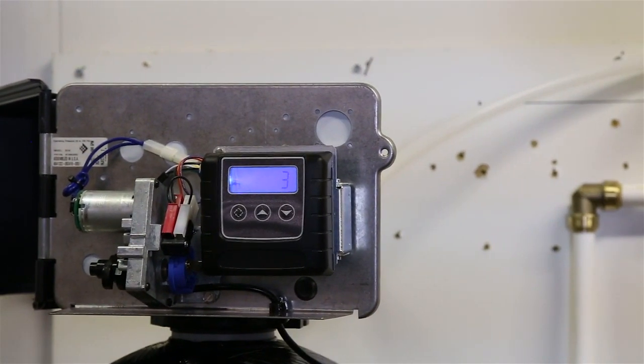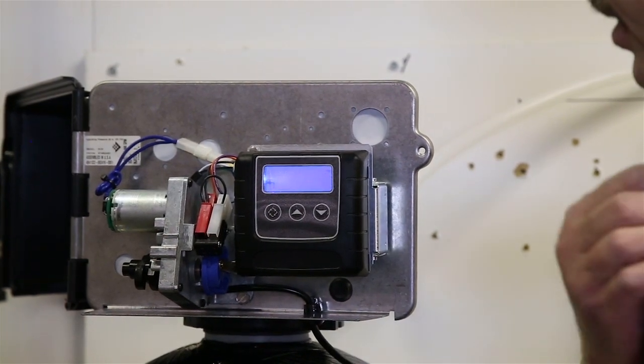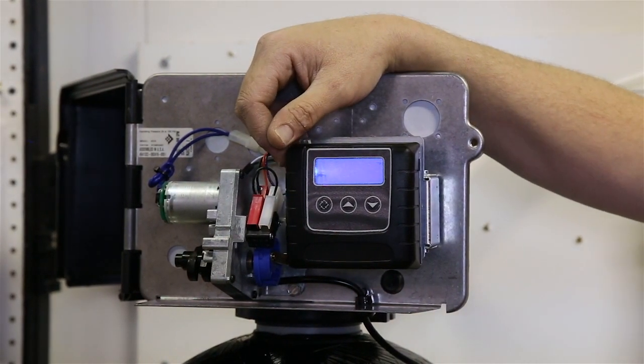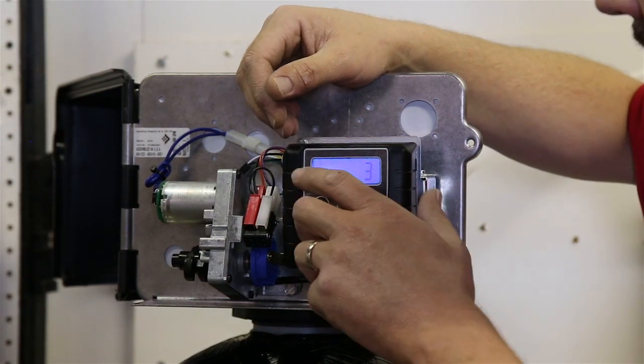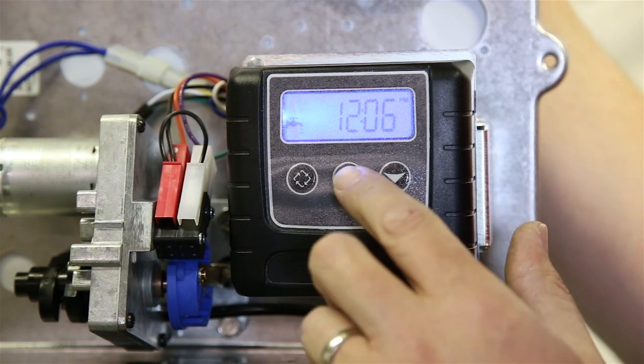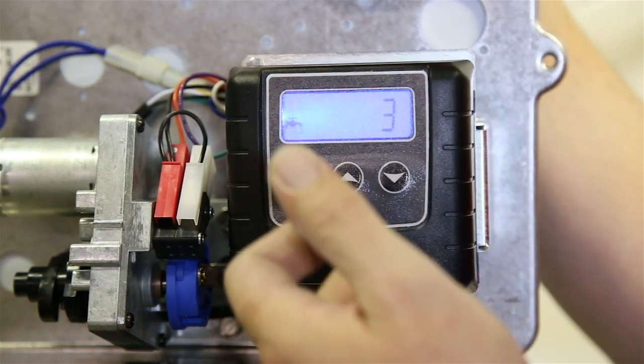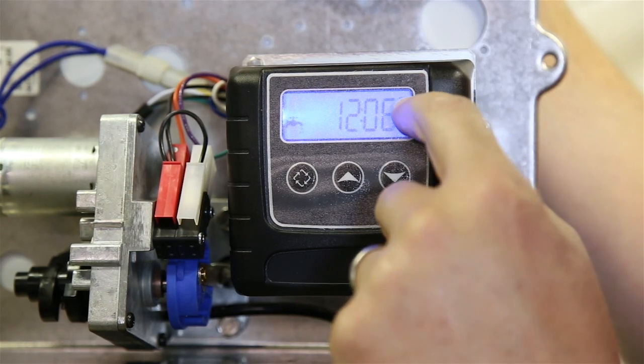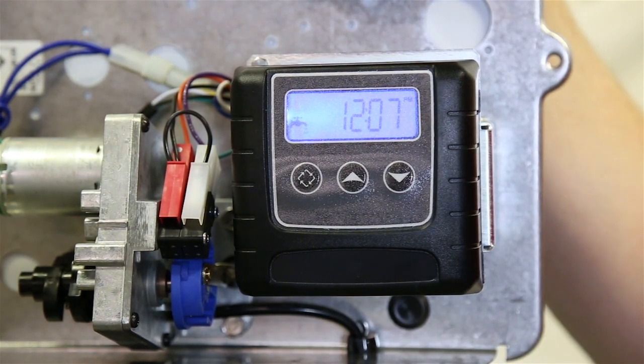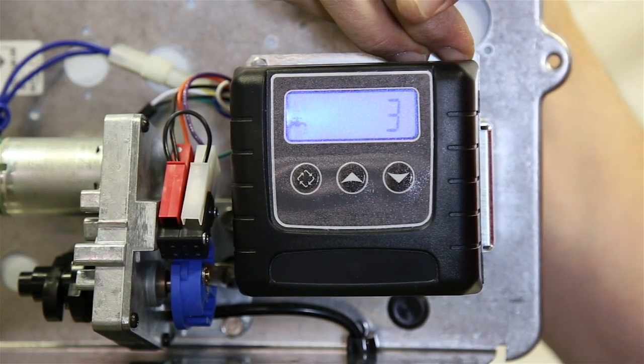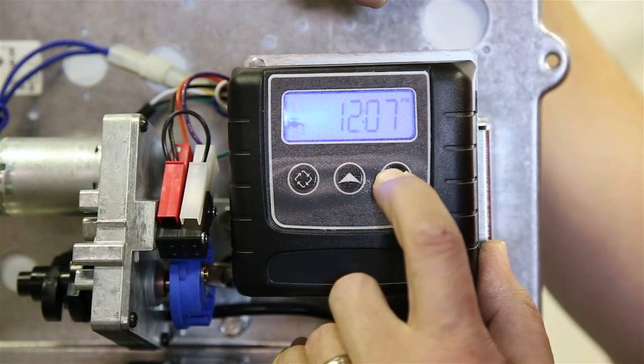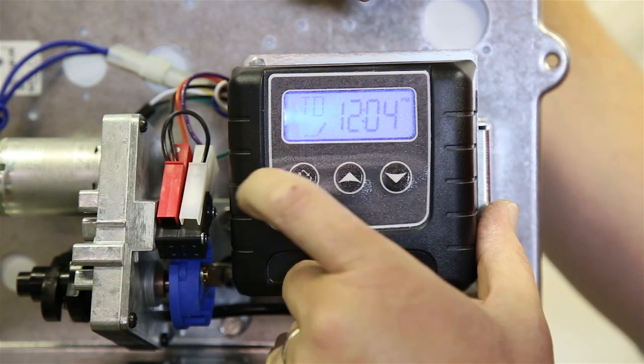So what we want to do is we want to check the programming first on this. And it's pretty simple to do. In order to get to the master programming mode on this particular controller, which is called a Fusion or an SXT control, you're going to have to change the clock to 12:01 PM. So to change the clock, we can push and hold either the up or the down arrow until we see the time start to change. You'll actually see a TD show up in the corner here and then a pencil with some dots.